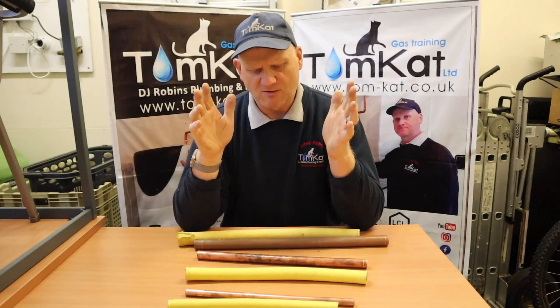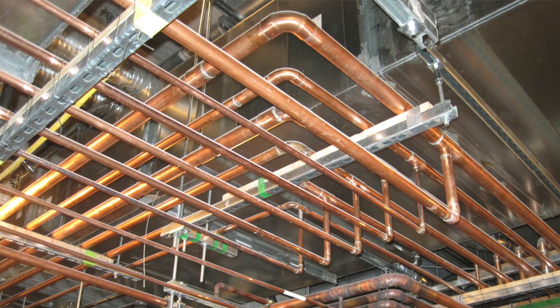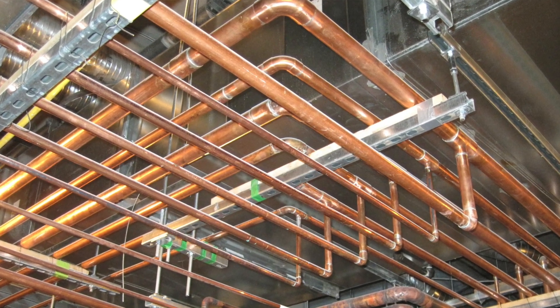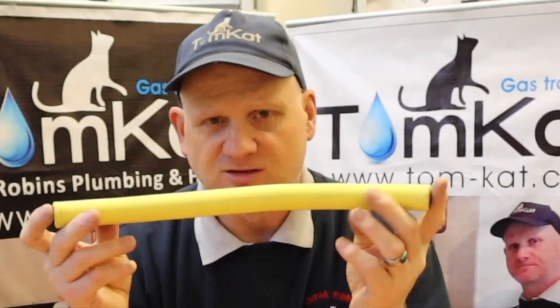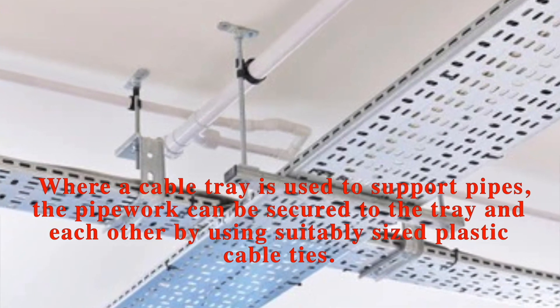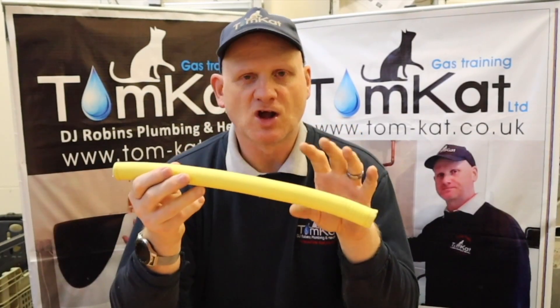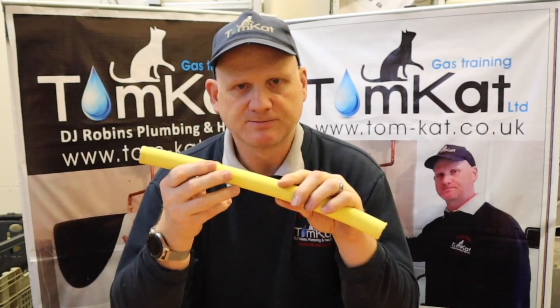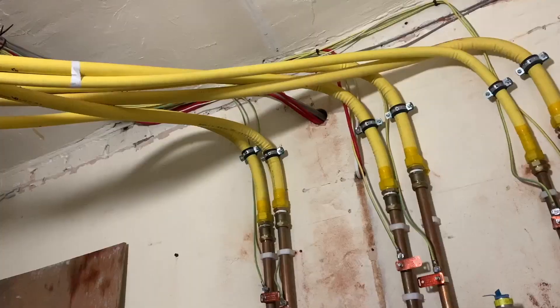One thing to be aware of is that TracPipe is nowhere near as rigid as copper. For long runs suspended from a ceiling where you could use Munsen rings and back plates with copper, with TracPipe you'd want to use cable tray to support its full length. Just think: if you're installing this, you need to install it in exactly the same way as copper pipe.